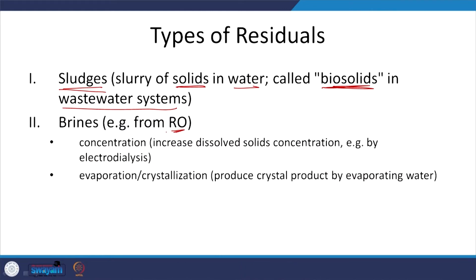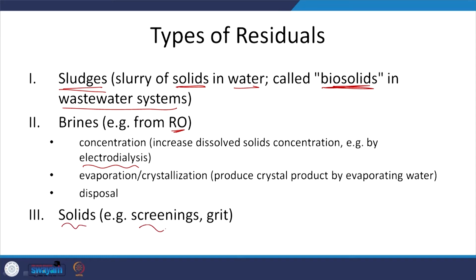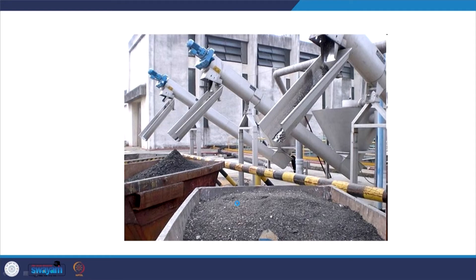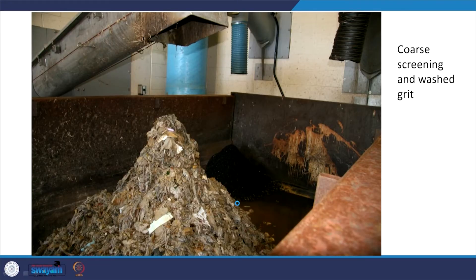This is a great disadvantage with RO — what do you do with this brine? Concentration — increased dissolved solid concentration, for example by electrodialysis. Evaporation or crystallization — produce a crystal product by evaporating water, and then disposal. Solids from screenings and grit — from preliminary treatment, we have the screw auger and then the grit washing chamber. Here you see an example of coarse screens and then washing grit. This is relatively more inert — different kinds of disposal. This will not go into any composting techniques.